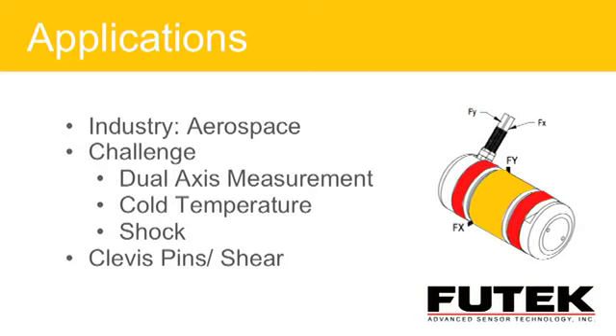They wanted to measure all the forces, and when a parachute releases it's not in a perfect condition—it may be out to one side. So we had to come up with a dual-axis measurement capability to measure Fx and Fy, so they could determine the vector forces generated. It also had to survive cold temperatures from the testing atmosphere, plus shock, since it's a fairly violent test. Imagine if the shock ruined the sensor and they didn't get the good test data they wanted.